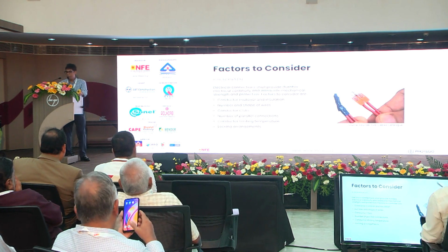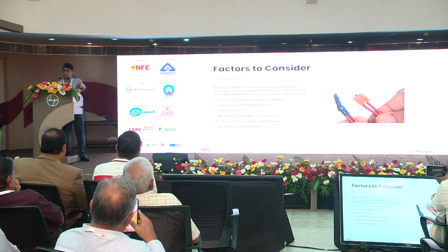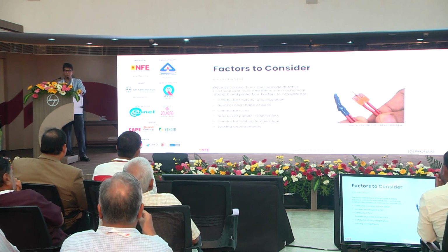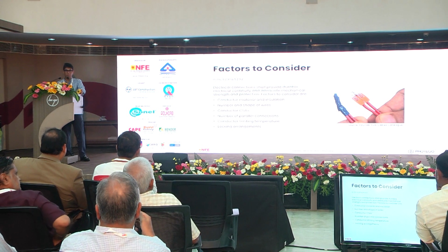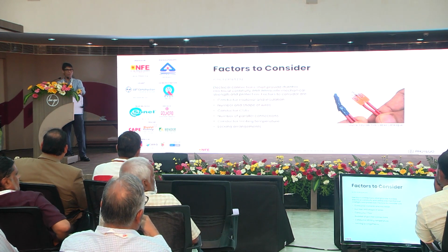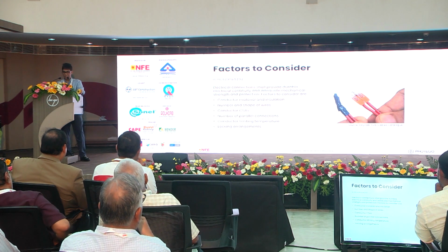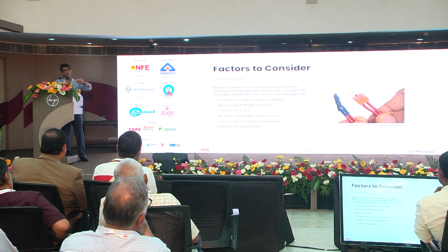Now, how many of you have seen a cable jointed? If there's one person that hasn't raised their hand, please, I want to know where you have seen a cable jointed properly. You've seen a cable jointed properly? Well, then you're one of the very few people that has actually seen one. See, very often proper joints like this in low voltage final circuits are not done. It is just somebody that twists and bends and puts it together.